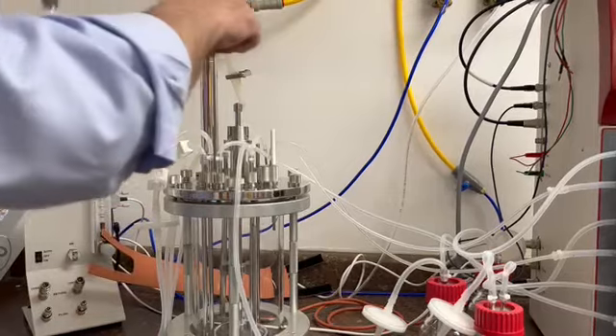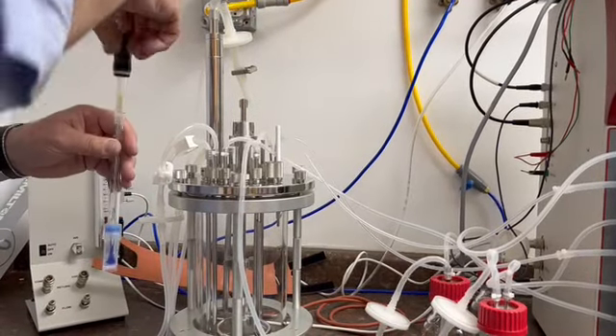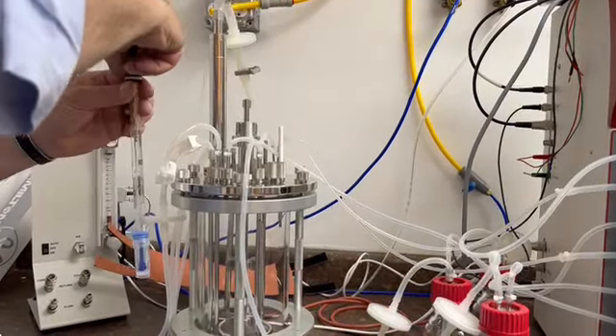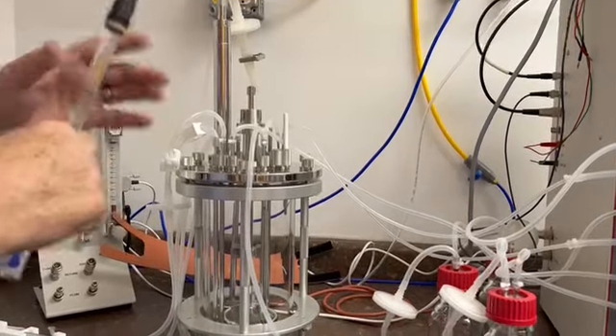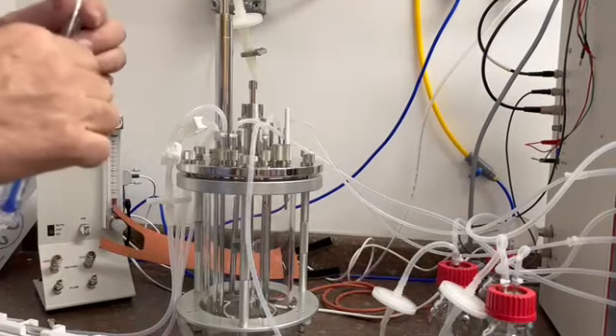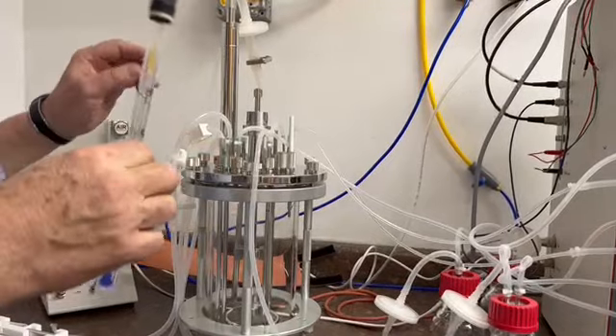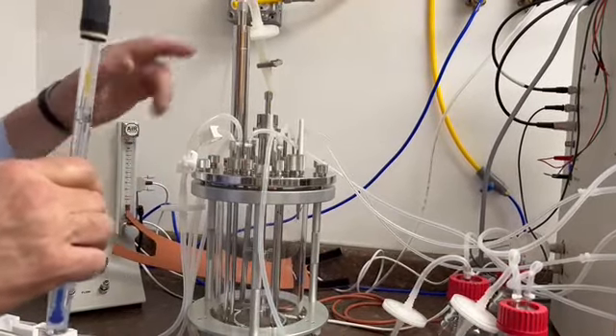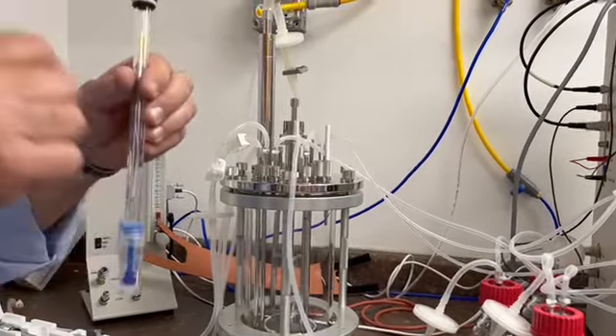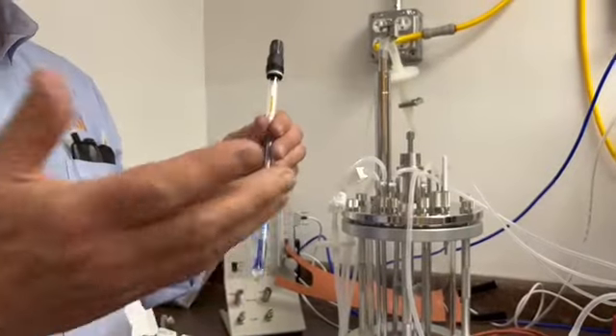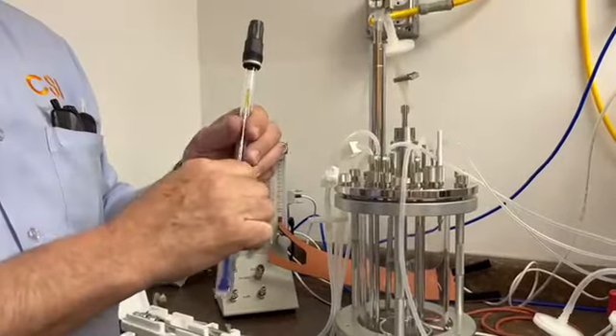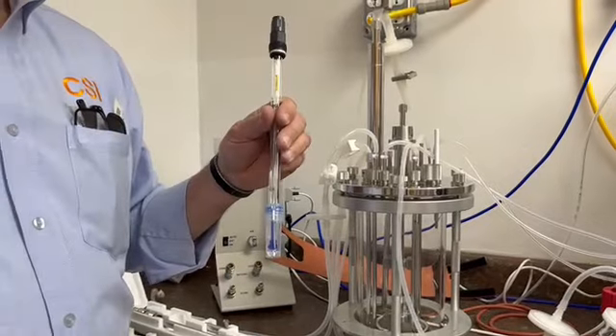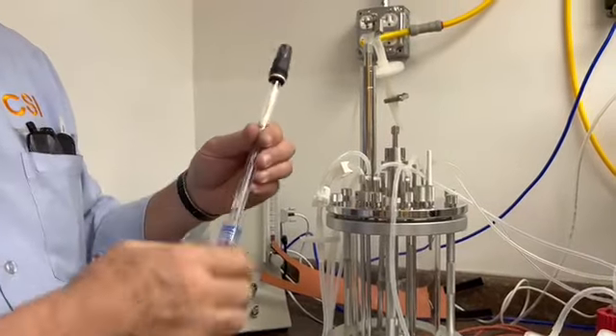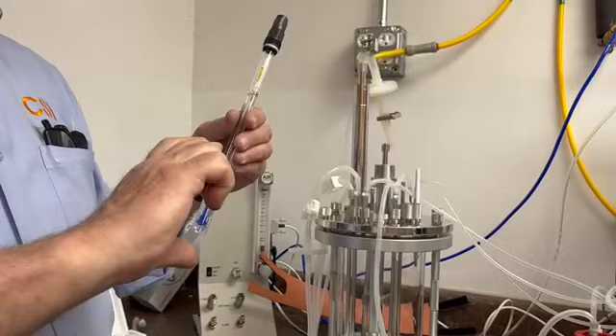Taking it out, feeding it through the O-ring, getting it down, and just threading it in until it's nice and snug. You know. Now this we would, prior to autoclave, just before autoclave, as a matter of fact, we would plug it in, and then we will calibrate it. Again, the built-in calibration routine is going to work the same as your benchtop units for the most part. Calibrate the pH probe before.